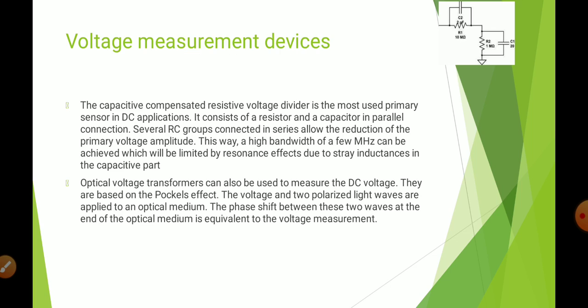Optical voltage transformers can also be used to measure the DC voltage. They are based on the Pockels effect. The voltage and two polarized light waves are applied to an optical medium. The phase shift between two waves at the end of an optical medium is equivalent to the voltage measurement. By this we can measure the voltage.